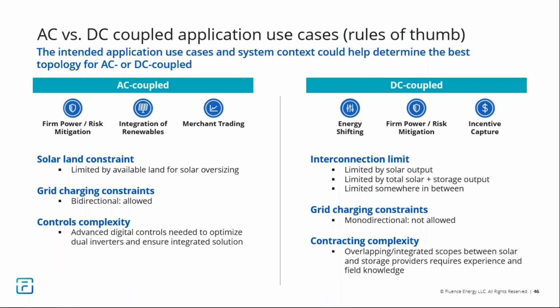There's often a tug of war between a constraint of land or a constraint of interconnection. When land is the limiting factor, often the solar cannot be oversized, so there's a reduced amount of clipped energy, which suggests AC coupling may be more beneficial. If interconnection is the limiting factor and there's ample solar space, DC coupling may favor your system, since you can oversize your solar relative to the interconnection or inverter size, creating significant clipped energy that a DC coupled system is better positioned to capture.